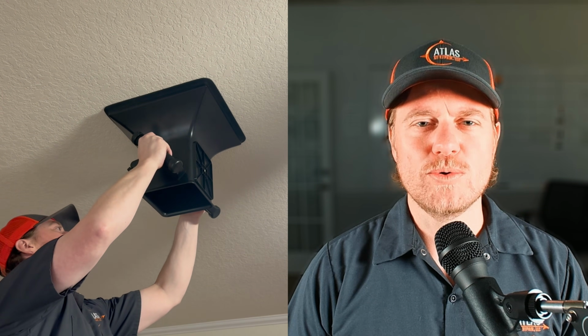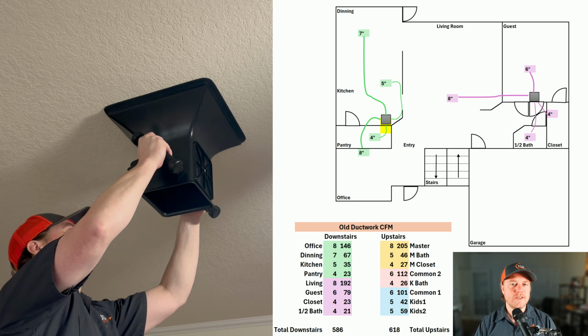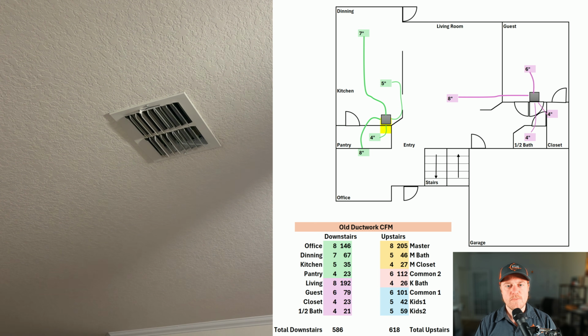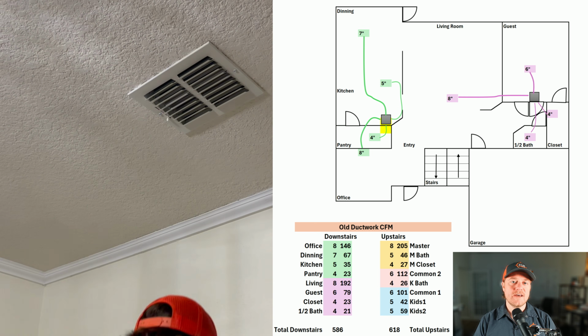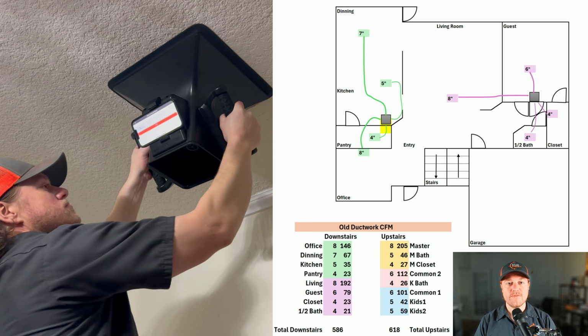Now that we have everything up and running, let's do some before and after airflow tests. What I'm doing now is going into each vent using this flow hood to get our CFM per vent. This is going to tell us what kind of airflow we're getting from the ductwork modifications that we made.